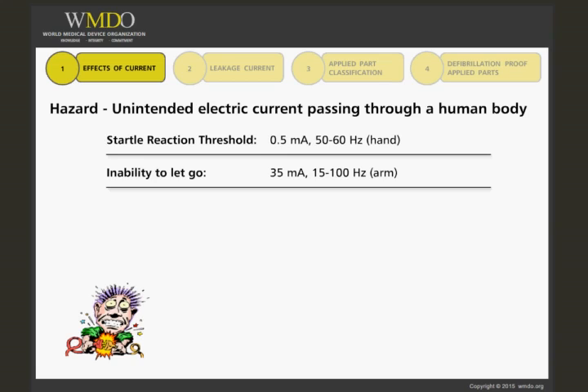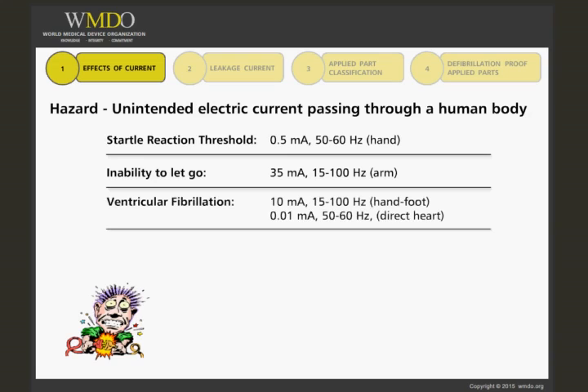The next level would cause ventricular fibrillation to the heart, caused by 10 milliamps, 15 to 100 hertz, hand to foot, or 0.01 milliamps — which is 10 microamps — 50 to 60 hertz, directly to the heart.